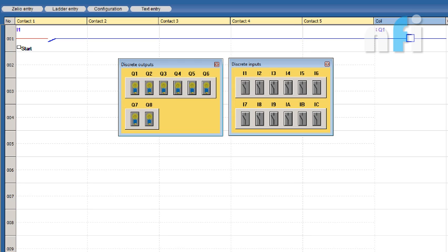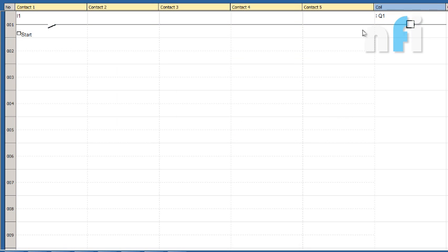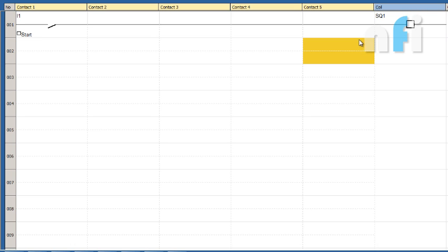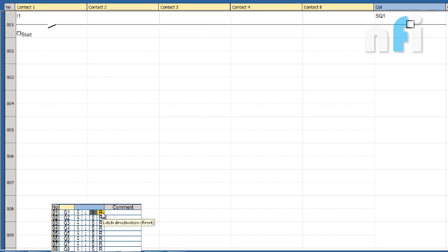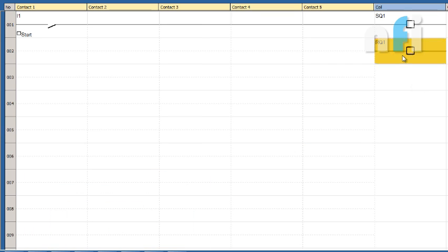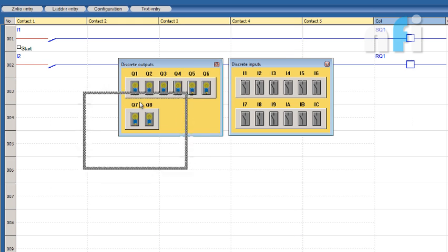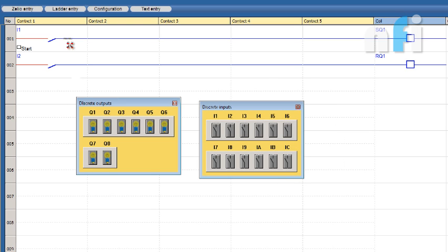Okay. So now coming to the interlocking using special commands. Instead of this impulse, I'll take set here. This is similar to impulse, but the difference is it will remain set. It will not get reset by the same pulse. To reset this one, I need to use the reset part of this bit, this R. Let me just have it here. So I'm going to take one more input, I2. Using that, this will get reset. So this will get latched and unlatched without using the auxiliary contacts at the bottom of the inputs.